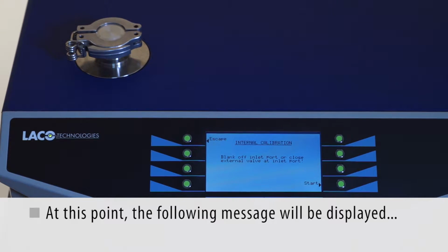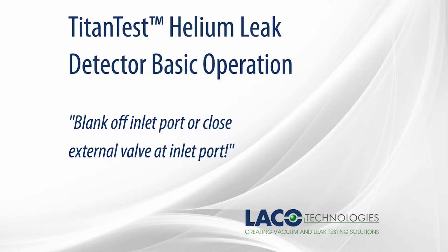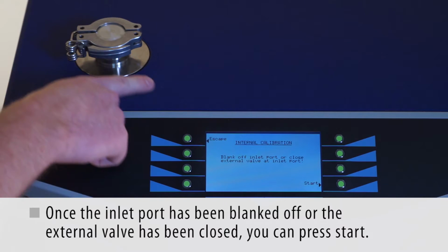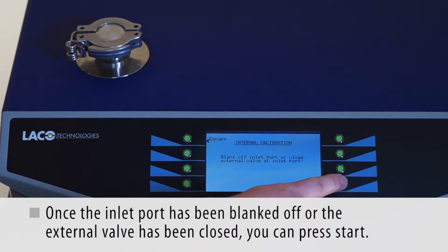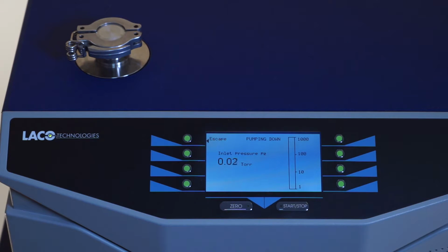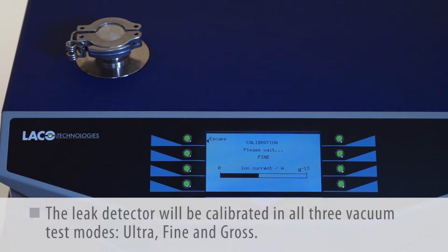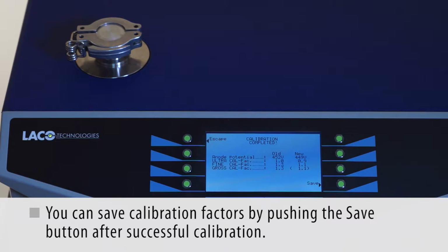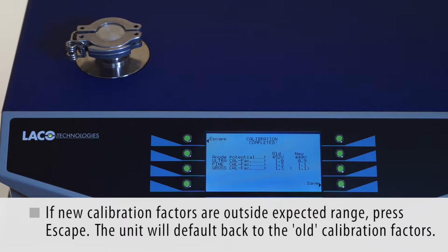At this point, the following message will be displayed. Blank off inlet port or close external valve at inlet port. Once the inlet port has been blanked off or the external valve has been closed, you can press start. The leak detector will be calibrated in all 3 vacuum test modes: ultra, fine, and gross. You can save calibration factors by pushing the save button after successful calibration. If new calibration factors are outside expected range, press escape and the unit will default back to the old calibration factors.